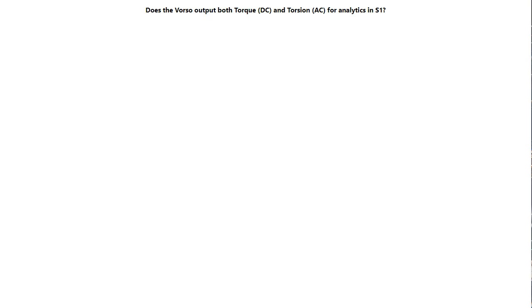Oh, sorry, John, I'll take that. I forgot to toss that to you. Or both of us, Brian or I, can kind of handle that one. So certainly the AC component, that's the torsional vibration coming through in System 1. And yes, you can trend the DC component or trend the overall torque values. Again, I'd say for trending purposes only in System 1, we wouldn't recommend using it, at least in this first release here, for anything beyond just the trending purposes. Our primary focus, again, is on the torsional amplitudes or torsional natural frequencies that are coming through.